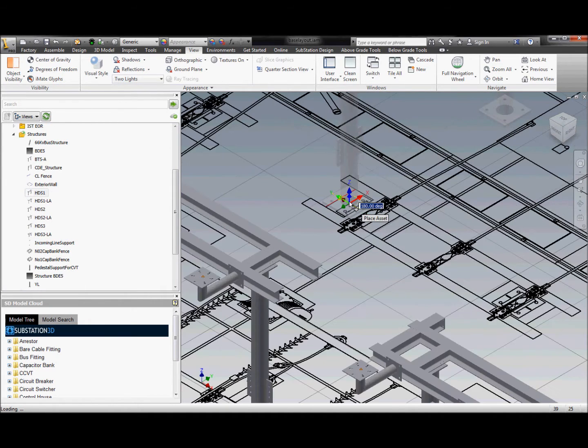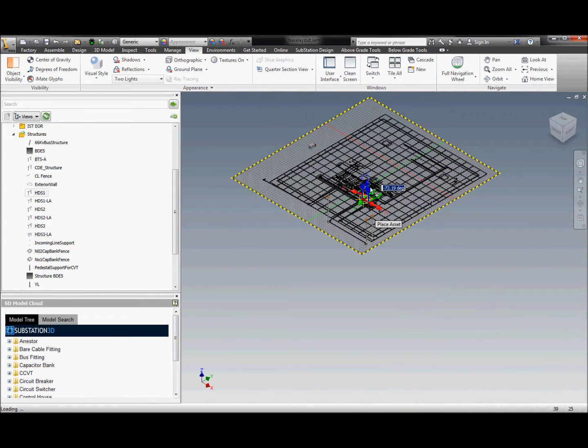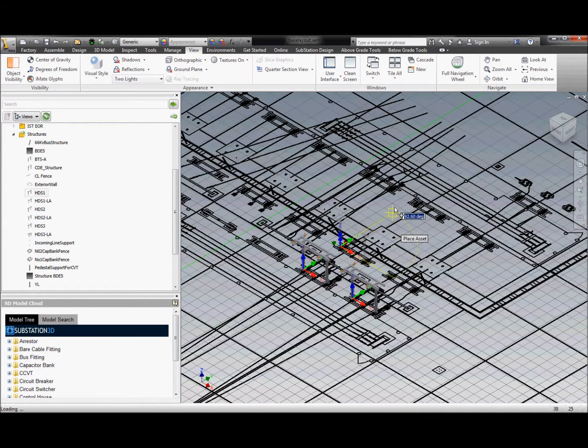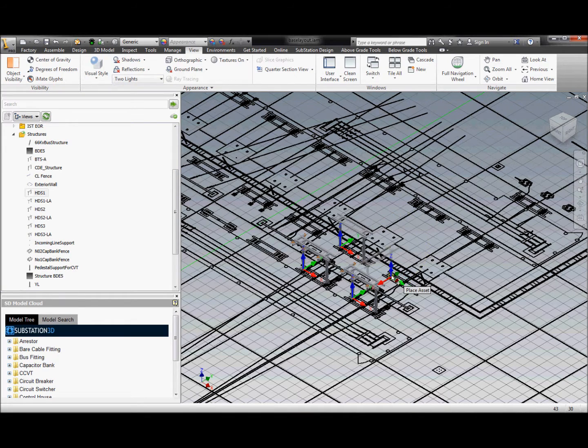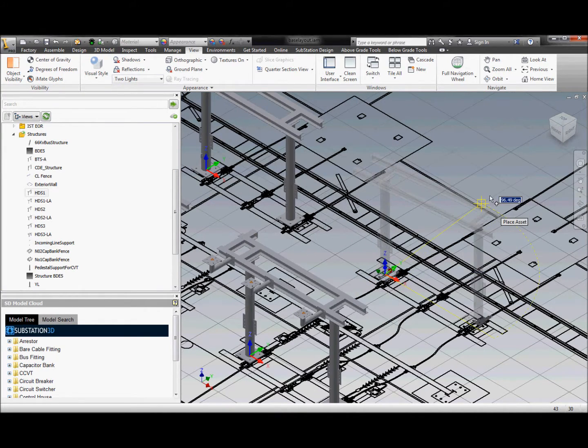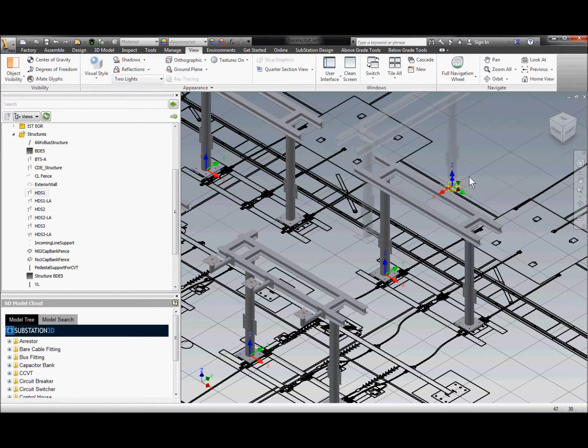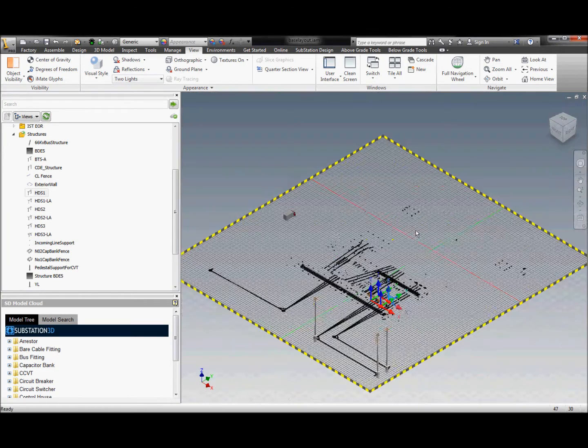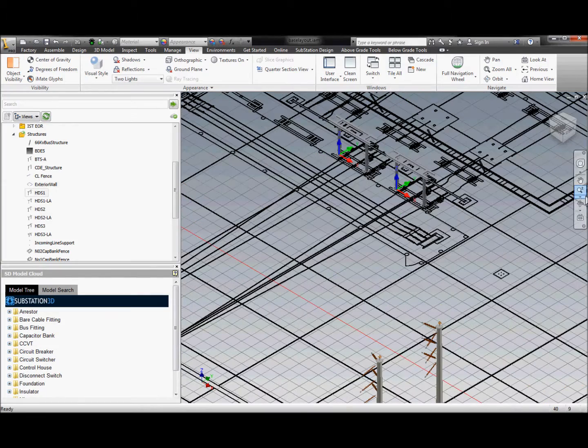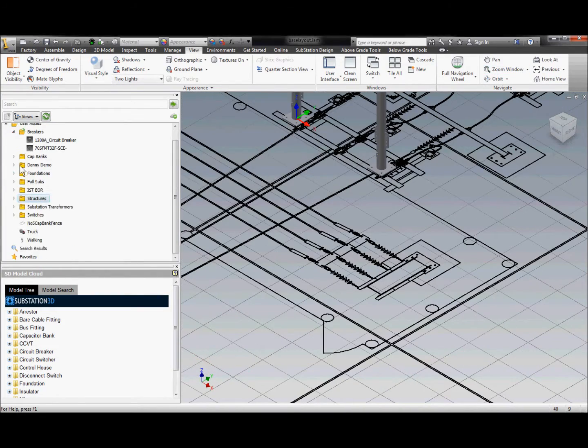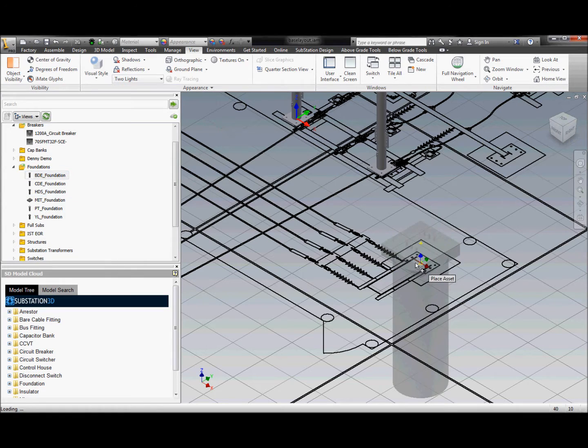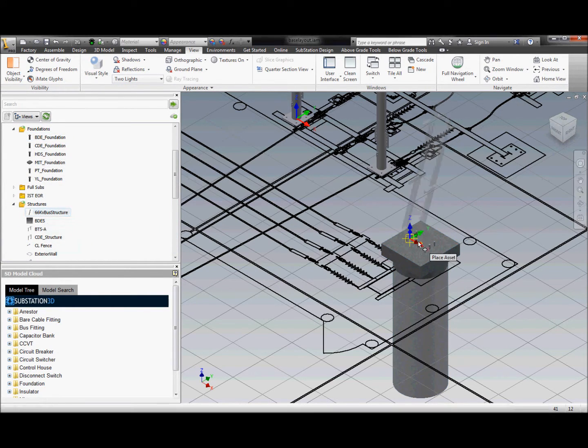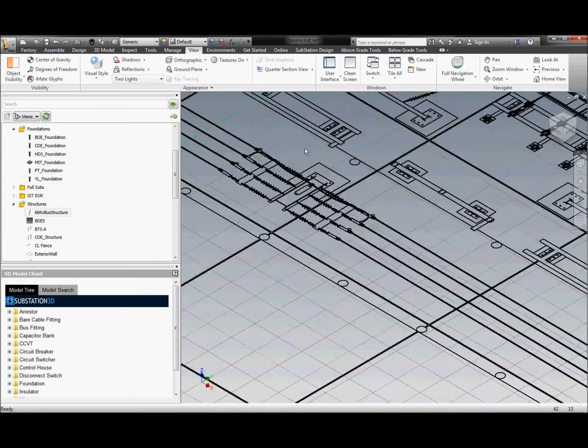All of the assets and components created for the substation models use that core plane, and that plane can be the top of the foundation with all the Z values adjusted up and down. To constrain a component we only need one reference point using the coordinate system constraints. This makes it very simple to snap together geometry — unlike in the past with some 3D systems where you had to have three constraints. This makes it very easy to quickly pull together a 3D assembly still using the 2D references from legacy AutoCAD data. Here we're snapping a foundation to a point, with the Z value already adjusted — about 22 inches from the ground plane.